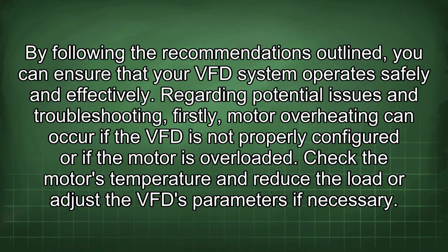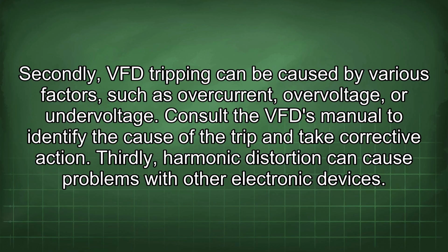Regarding potential issues and troubleshooting, firstly, motor overheating can occur if the VFD is not properly configured or if the motor is overloaded. Check the motor's temperature and reduce the load or adjust the VFD parameters if necessary. Secondly, VFD tripping can be caused by various factors such as overcurrent, overvoltage, or undervoltage. Consult the VFD manual to identify the cause of the trip and take corrective action.